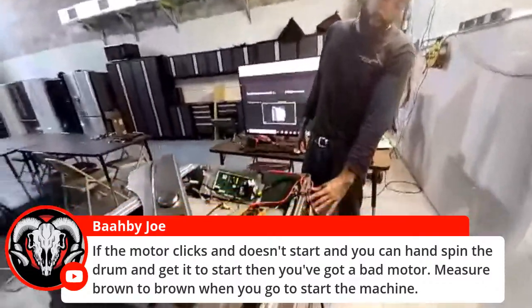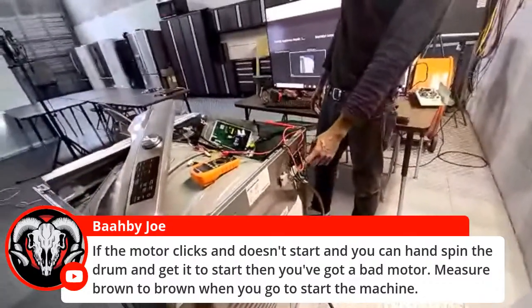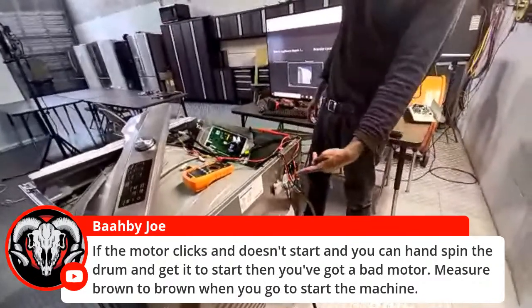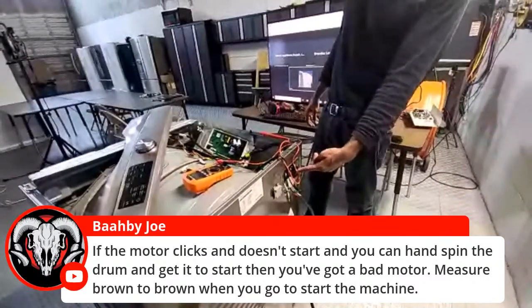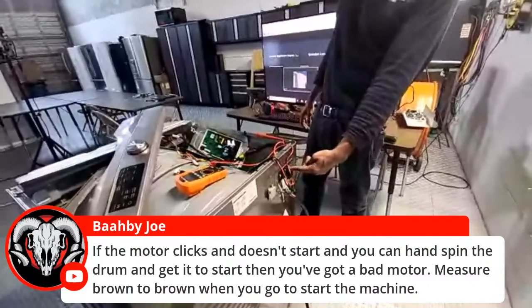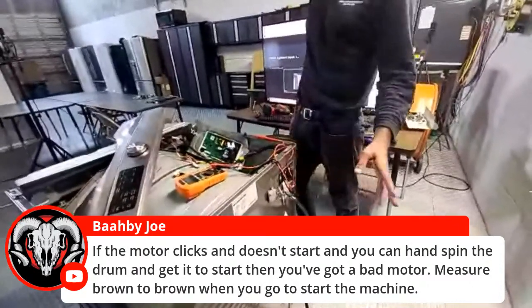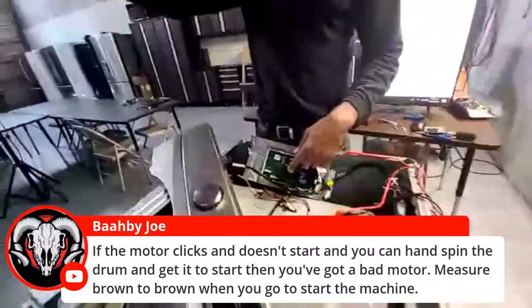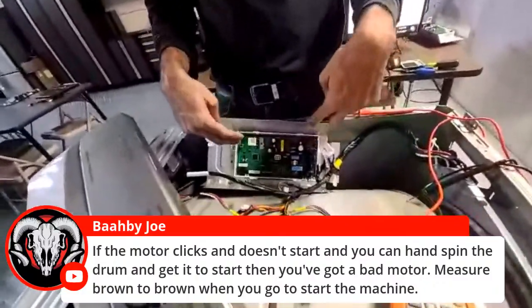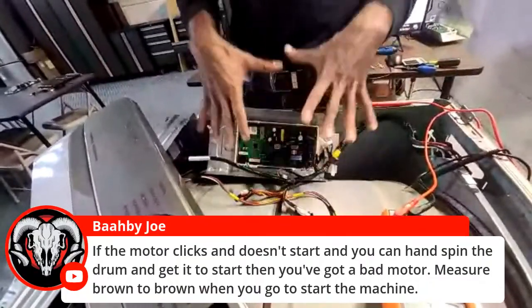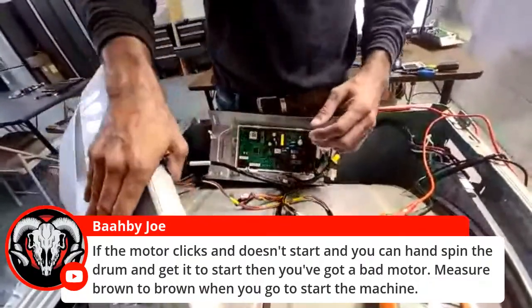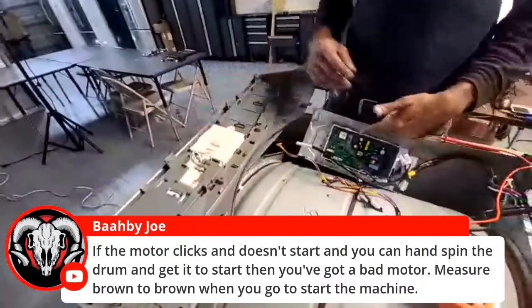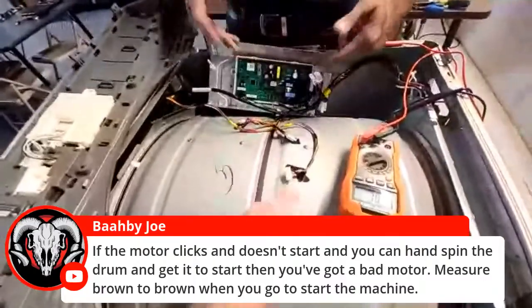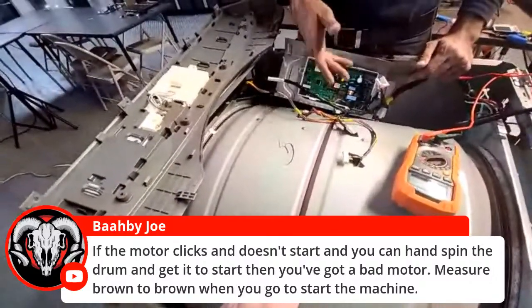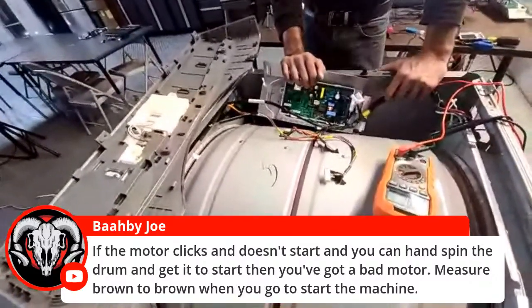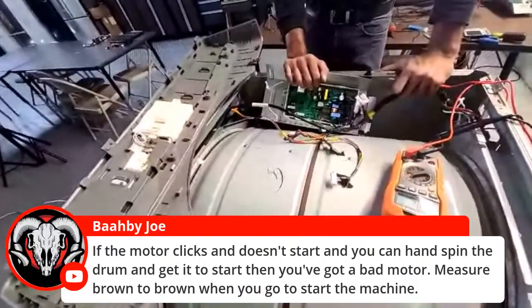We verified at our terminal block we had our correct wire configuration. We had 120 to neutral, L1 to neutral. We had 120 to neutral, L2 to neutral. So we know, and we had 240 across. Then we made sure we went to the schematic, made sure we had proper input voltage to the board now. Brand new board, output VDC, we weren't getting... we haven't checked output voltage, right? We did, and yeah, that's what you check from the plug here. So then we're not getting output voltage when you have a bad board. It would help if we knew which two wires gave us the output voltage.